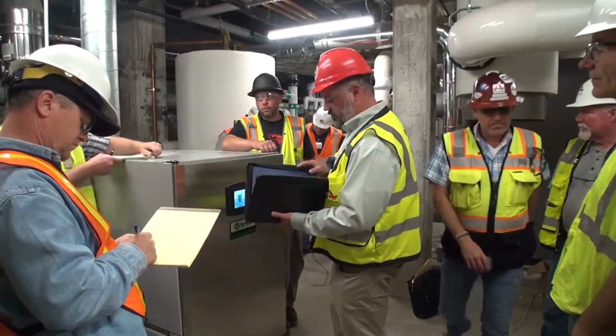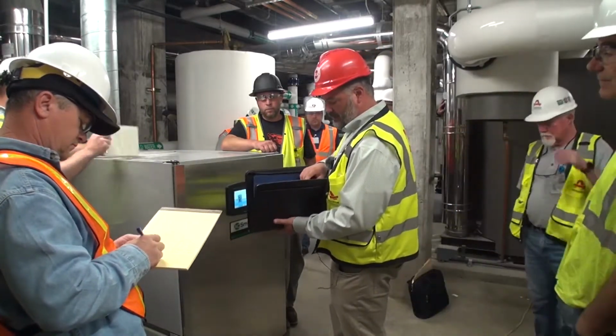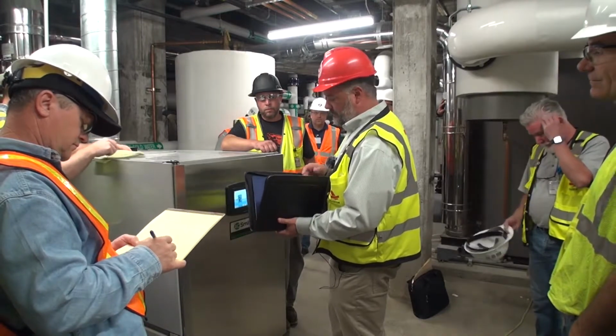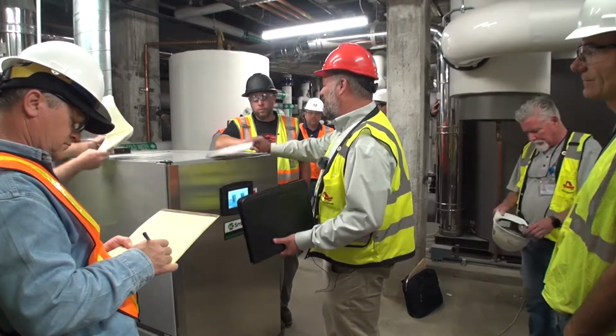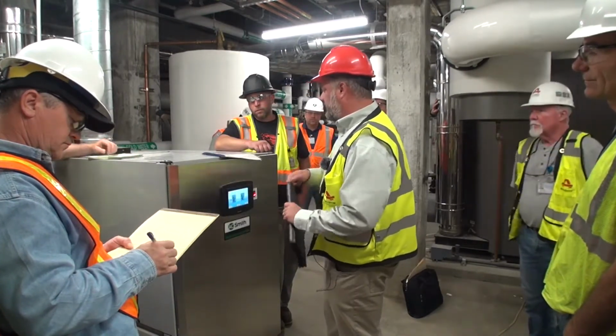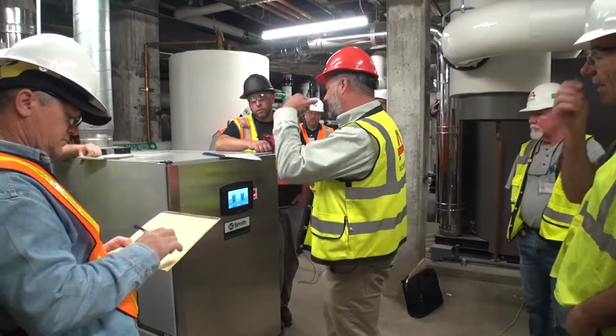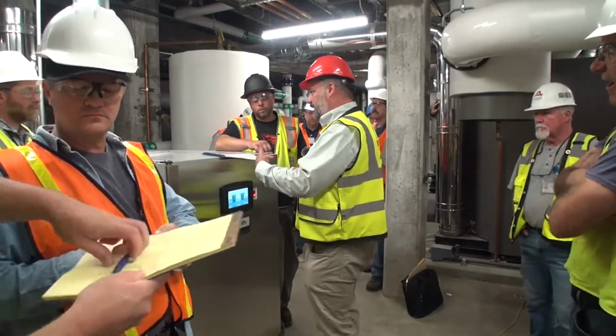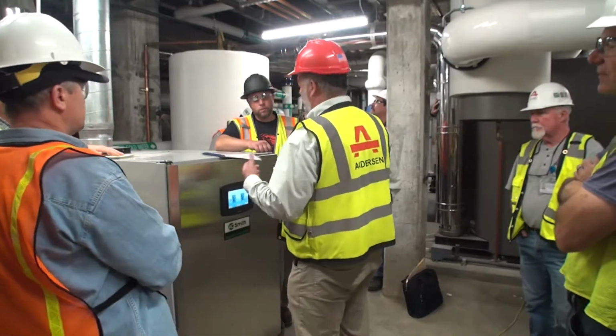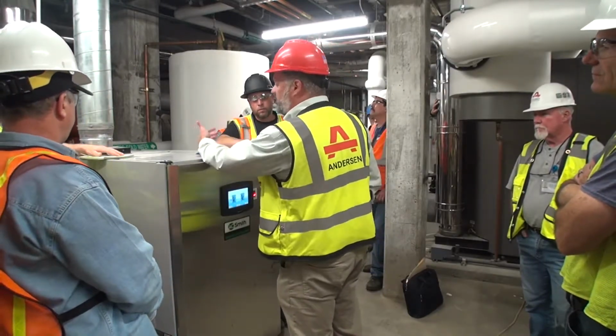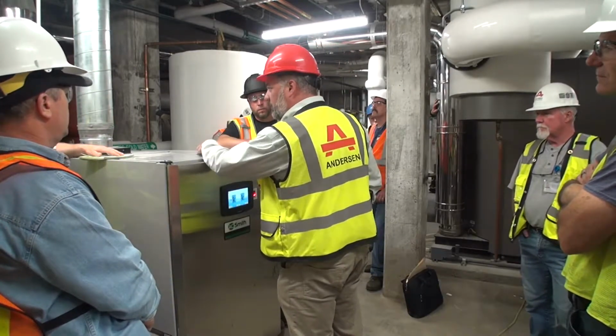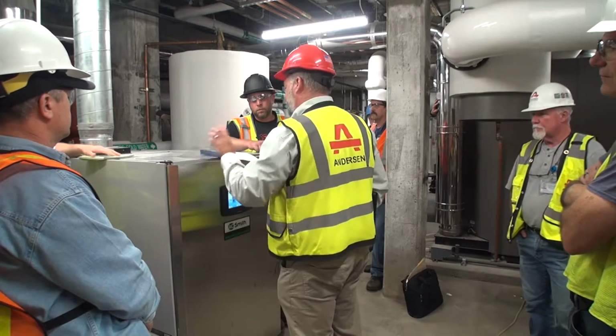The heat exchangers you can flush. I would recommend once every couple years on there. I mean, our water is pretty darn good, and this is a stainless burner train, stainless exchanger in here, so it's not going to get too bad, but flushing every couple years helps preserve that. So just flushing out the heat exchangers to work with.